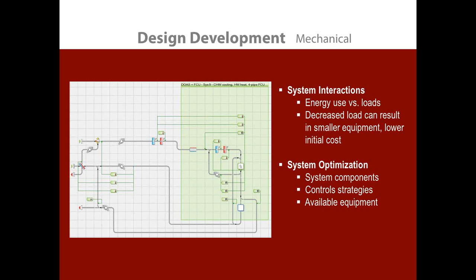So this is an example of that. We had a fish lab up in northern Michigan, and they need a lot of processed water for their fish tanks. We need to heat and cool that processed water to keep the fish happy and do their experiments. So we're bringing in water from the lake into this big 1,000,000+ gallon storage tank. We figured there's got to be something we can do about it. Start off with the baseline system, which is just a boiler and cooling tower that feed a heat pump loop, and each of these heat pumps distributes the heat either to the fish tank or the space.